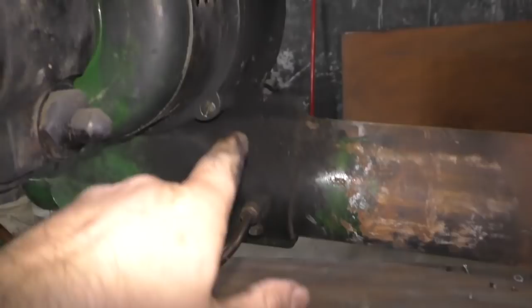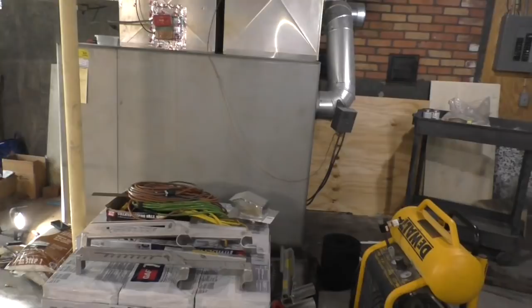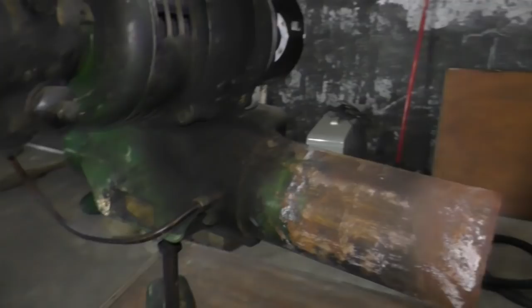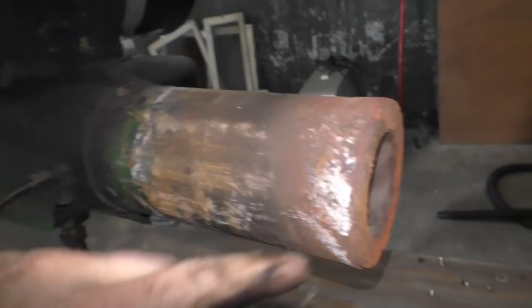This right here is likely caused from the issue I was talking about earlier. I don't know if it made it into this particular cut of the film, but those stack switches - the delayed cutoff for a failed ignition attempt is so great that it will allow the combustion chamber to fill up with oil mist. Then once it does ignite, because some bonehead comes down and presses it again, hey, maybe it'll happen this time - that might explain why the transformer was replaced at one point. But what happens is that causes a puffback situation. As soon as it ignites, boom, you've got a blast of combusting oil mist and air just blowing out of here. And that's what all this is from.